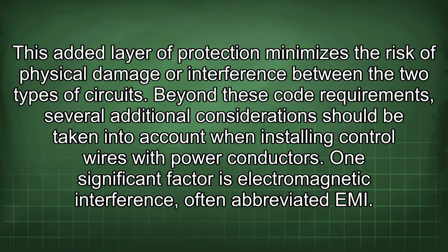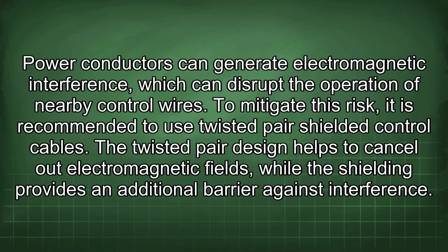Beyond these code requirements, several additional considerations should be taken into account when installing control wires with power conductors. One significant factor is electromagnetic interference, often abbreviated EMI. Power conductors can generate electromagnetic interference, which can disrupt the operation of nearby control wires. To mitigate this risk, it is recommended to use twisted pair shielded control cables. The twisted pair design helps to cancel out electromagnetic fields, while the shielding provides an additional barrier against interference.